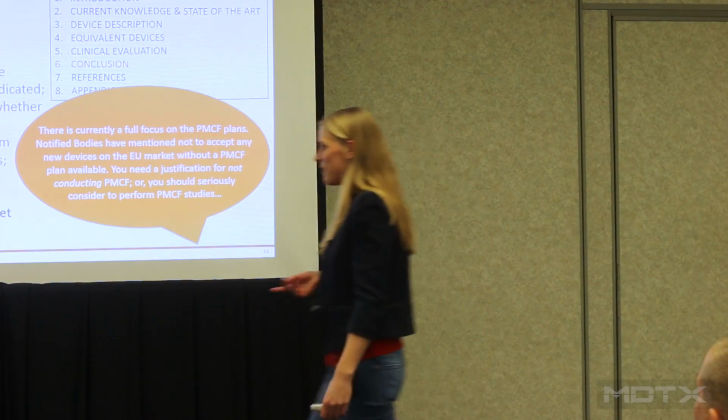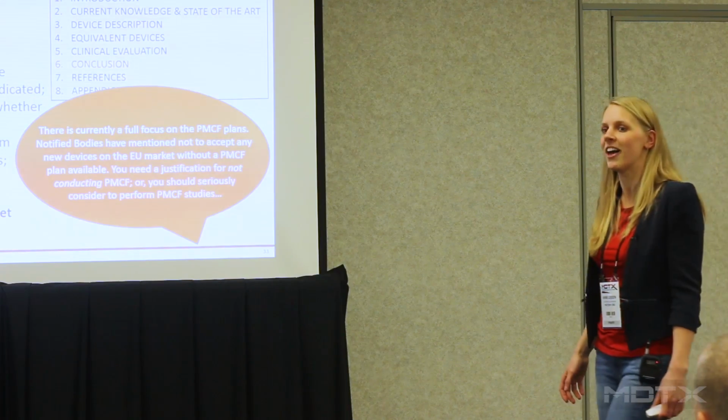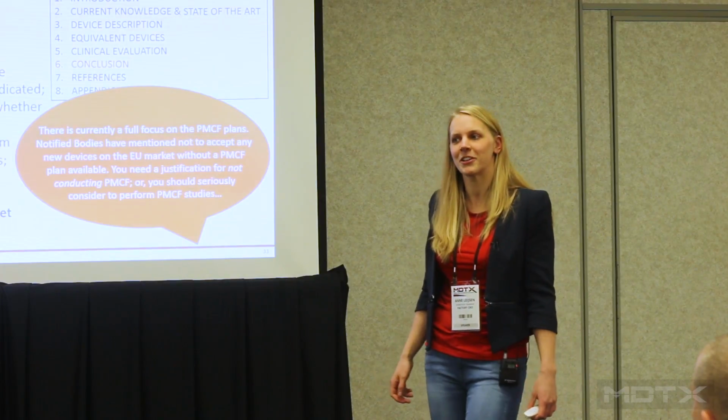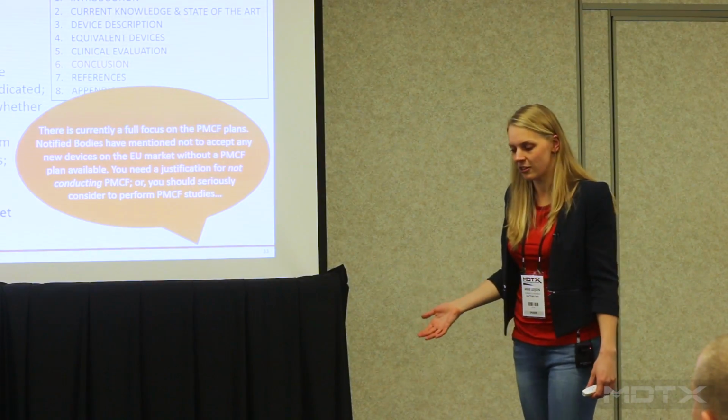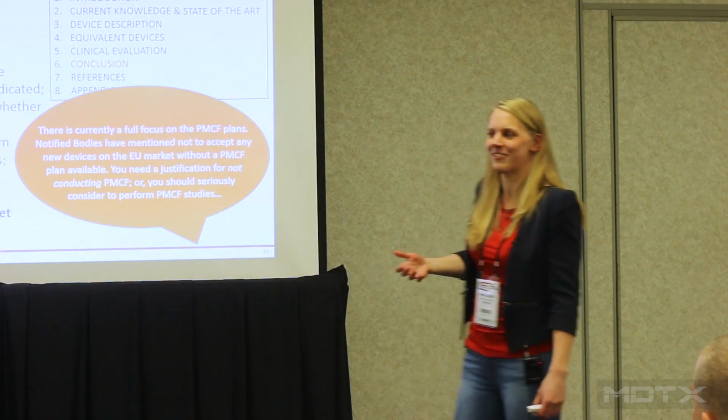And then this is an important one, circling back to the whole story on what the MDR expects and what all those other ISO requirements expect, the bigger picture that Christine pictured: outline whether there's a need for post-market clinical follow-up. Notified bodies nowadays do expect, for new devices, that you will have at least a post-market clinical follow-up plan available. They don't tell you that you have to say there that you're going to do a post-market clinical follow-up. Your plan might be that you're not going to perform one. I do think they expect you to perform a study, but they are not very clear on that.